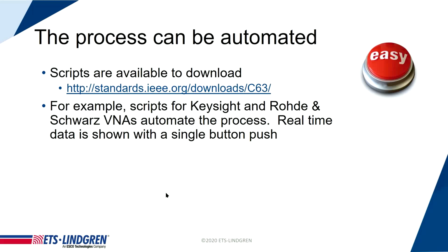The whole process I described is done in the background, because the time domain transformation is a function that's in a lot of network analyzers. So the script would take advantage of the analyzer's capability to do that transform, and all the post-processing and analysis of the data is done by the script. So you will see this process when my colleague runs the test. We're not doing these kinds of calculations by hand.